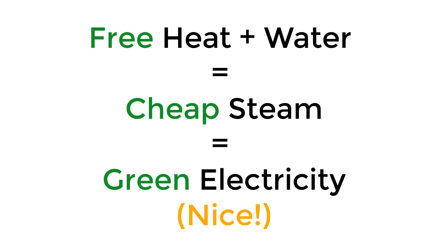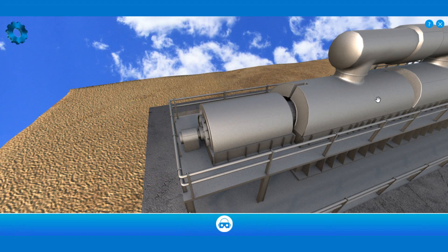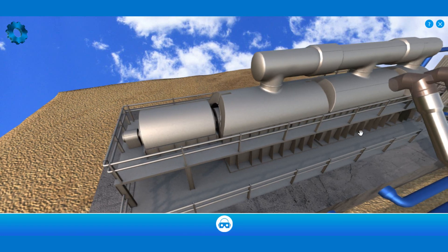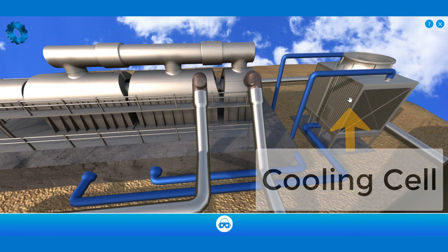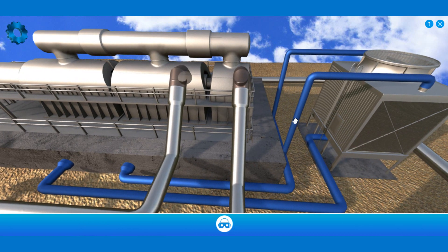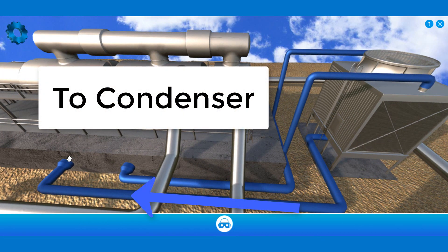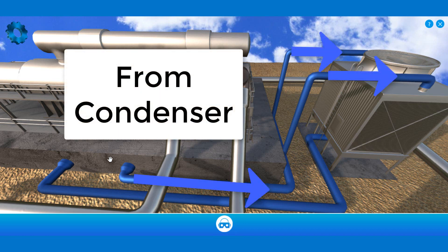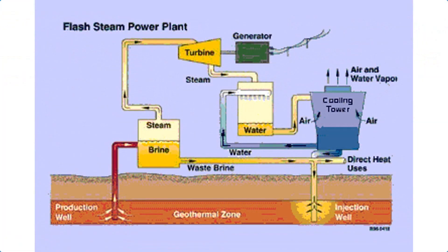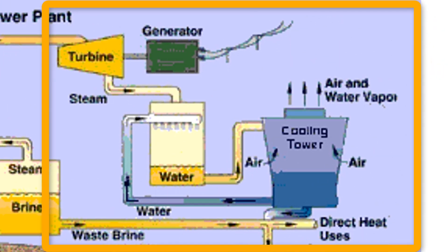So unlike a coal-fired power station, we don't need to create a fire or heat source — we just use the heat from the Earth. Now we're making electricity, and all of that steam needs to be condensed so that it can be injected back into the Earth again. What we'll use is a cooling cell. Water from the cooling cell will come out, go down into a condenser, and condense the steam we no longer need for the turbines. It'll then get rid of heat energy by being passed through the cooling cell, releasing that heat to the air, before being sent back to the condenser again.